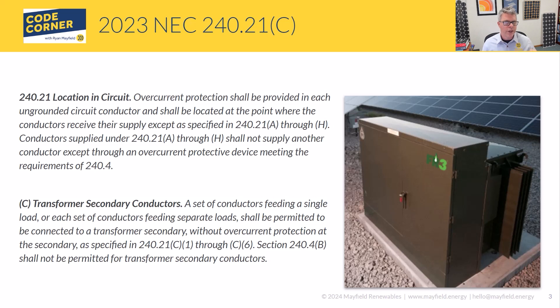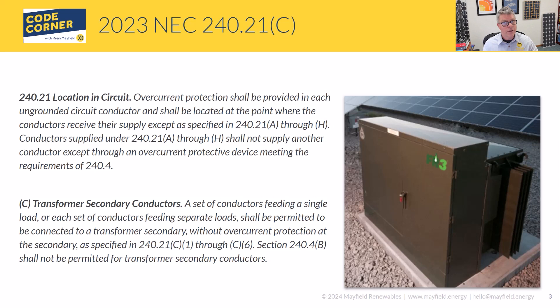One big thing to point out is the last sentence in 240.21C: 240.4B shall not be permitted for transformer secondary conductors. 240.4B is the allowance that lets us protect conductors with an overcurrent device rated higher than the conductor's ampacity — a common application in sizing conductors. What this tells us is we can't apply that here. So if you install an overcurrent device, the conductors must have an ampacity of at least what that overcurrent device is rated. We can't round up to the next size as allowed in 240.4B.